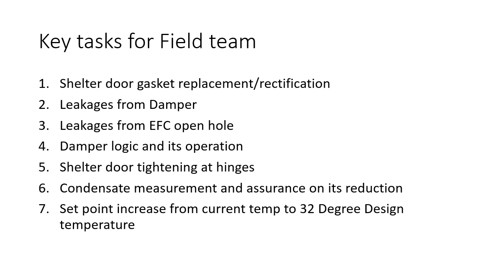After doing all rectification for shelter leakages, again the condensate has to be measured and you have to see the difference. If there is a difference, it means whatever leakages have been arrested have turned effective and have increased the overall efficiency of the compressor.